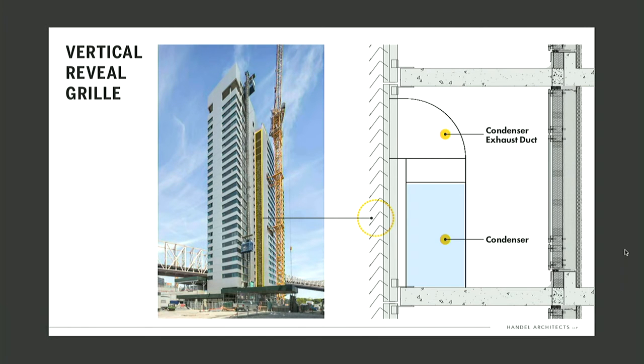So we have this grill that became a primary part of the architectural expression. And so it's bringing in air here and then directing the air out. The reason why we have this ductwork above the condensers is that you really want to force the air out. Otherwise, you want the air to go out that way. You don't want it to short circuit all the way up the building, because by the time you get to the condensers that are up here, they won't work. And so it is very important to have enough space in your condenser porch for the equipment to function.